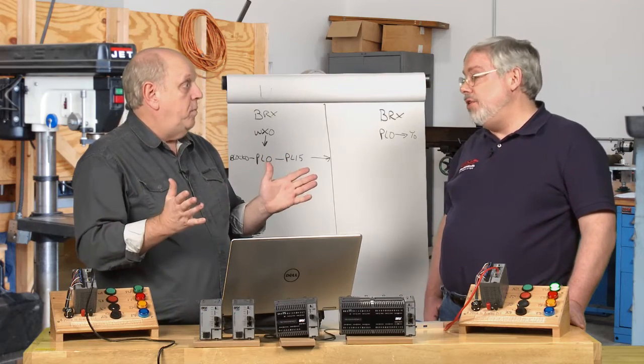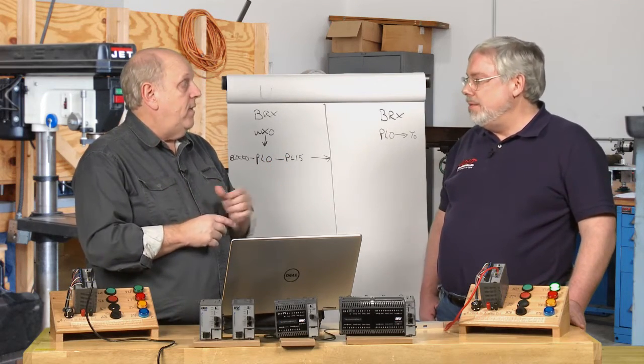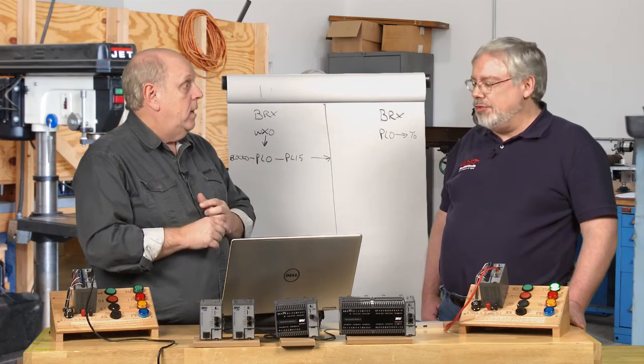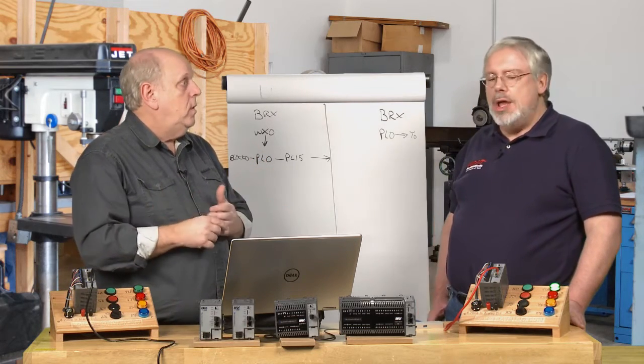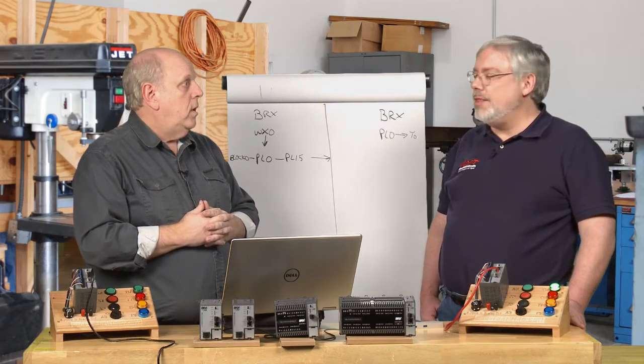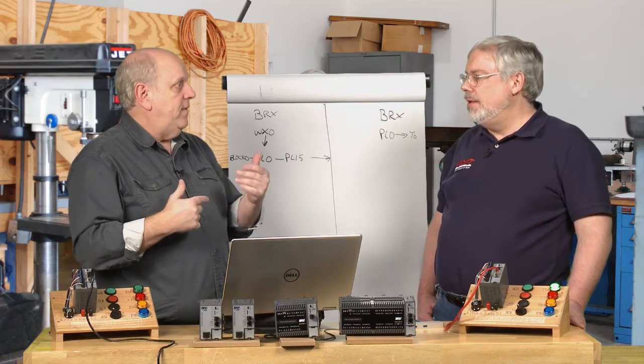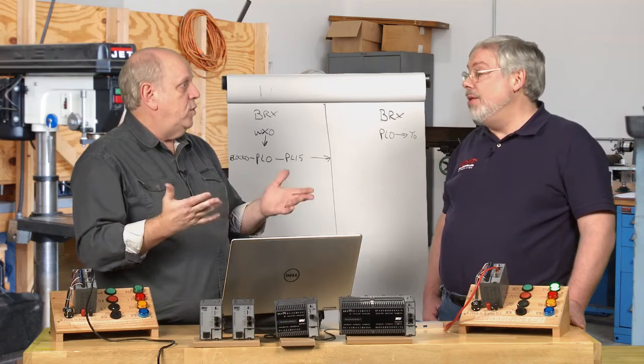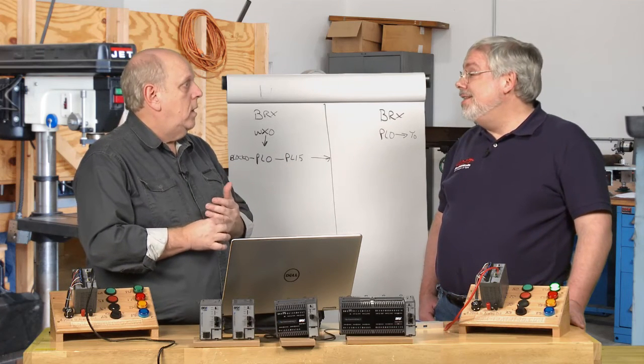They don't do PeerLink. Even if I had the card, they don't do PeerLink. It's only the ones with built-in ethernet, same with the 205 and Terminator—it's only the ones with built-in ethernet. If you have a 205 that doesn't have ethernet on it, just USB, it won't do PeerLink.